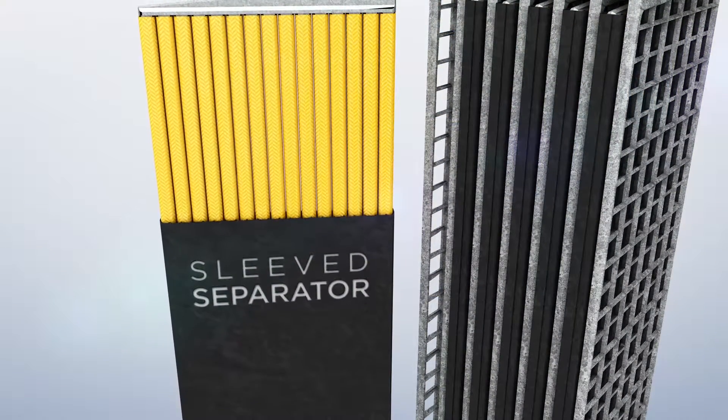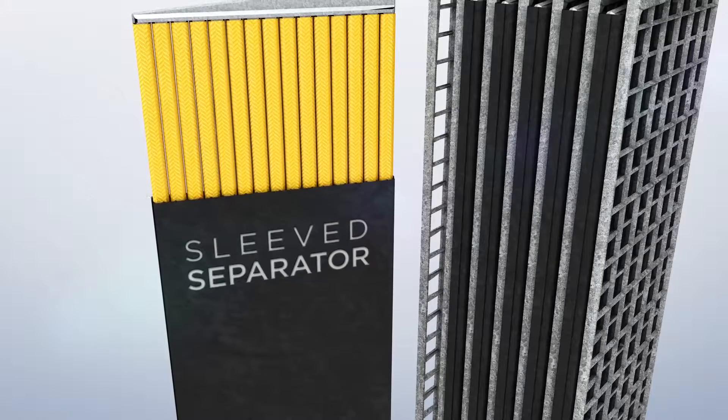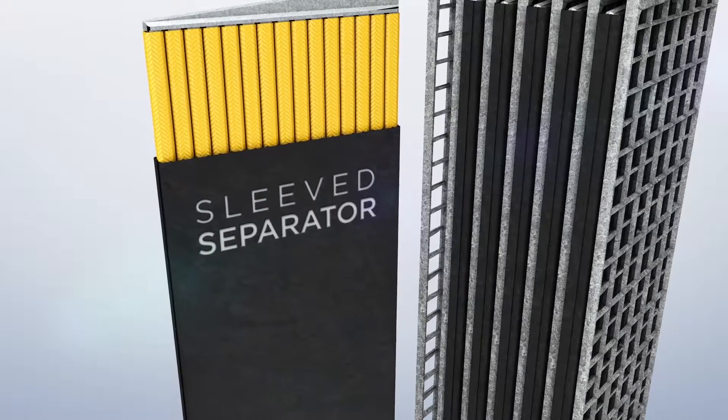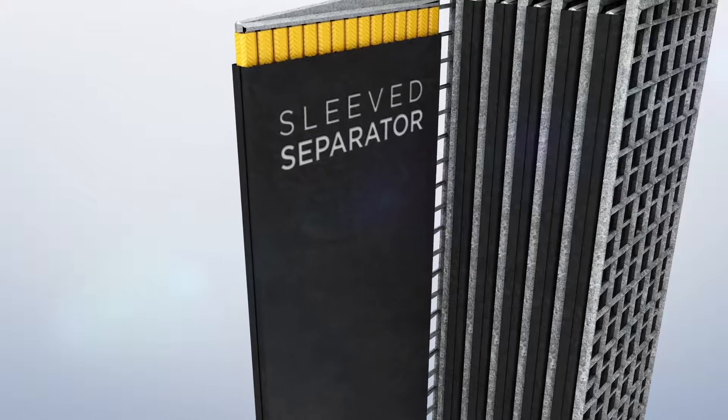A full sleeve encases the positive plate to eliminate shorts and potential problems with misalignment. The sleeve also prevents shorts between the sides of the plate, and the unique back-rib design increases electrolyte flow and maximizes contact with the negative plate.